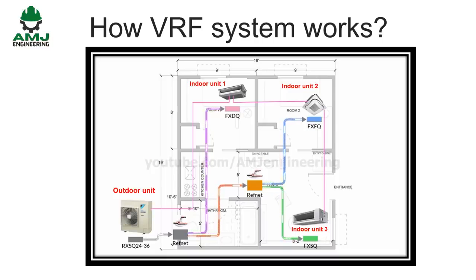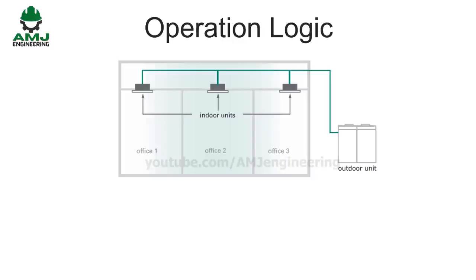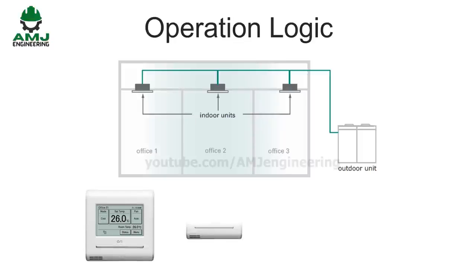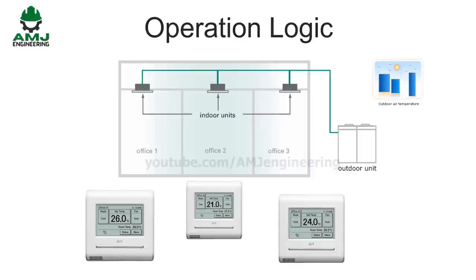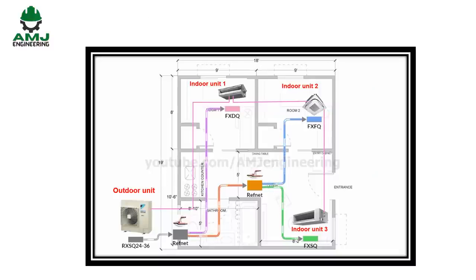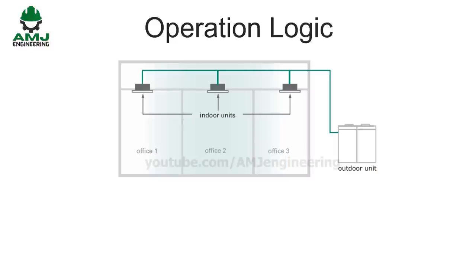How does VRF HVAC work? The operation logic of the VRF is fully built into the system and is proprietary for each VRF manufacturer. The system gets inputs from the user, for example the desired comfort temperature, and from the surroundings, for example the outside ambient temperature. According to that data, it implements its logic in order to get to the desired comfort conditions, utilizing optimal power consumption. Let's see a typical example.